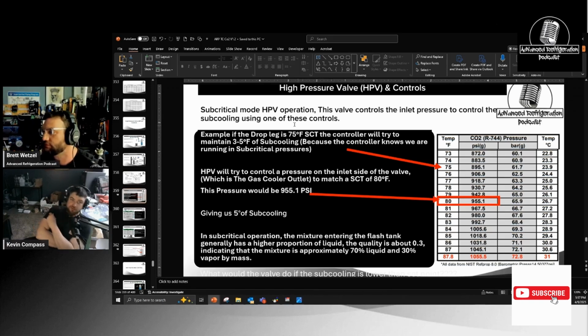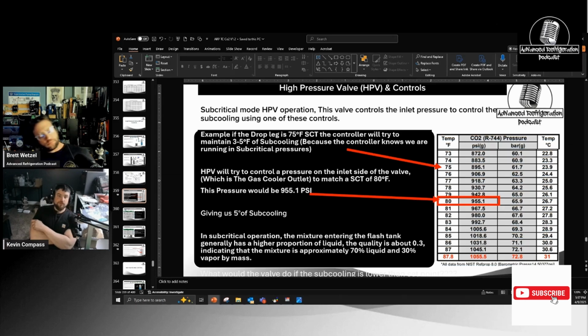Correct. And here's another issue that is a common one that we run into: the rack's been down for a while, or you shut the rack down for maintenance and you're going to start it back up. And you're using a sensor that's mounted at the outlet of the gas cooler, which I absolutely hate. I'd rather be inside the rack. So at the outlet of the gas cooler, you have a temp sensor. Say it's on a metal roof or on a roof where it's just insulated on the drop. If it's down long enough, that heat is radiating off that roof right through that Armaflex, and that piping and that gas cooler picks it up. That sensor may be so warm from it sitting off, 90, 95, 100 degrees.